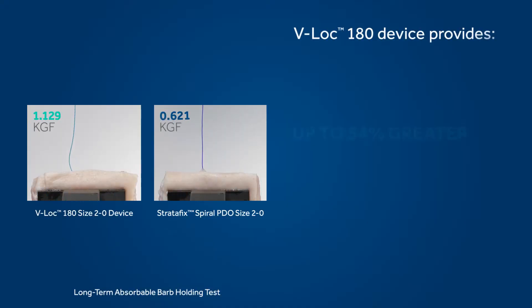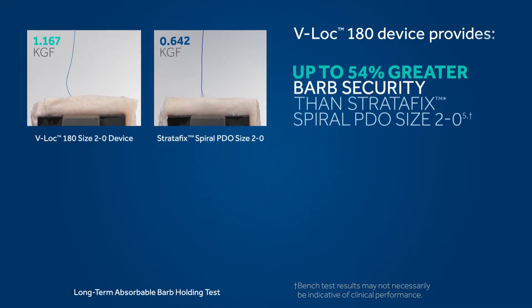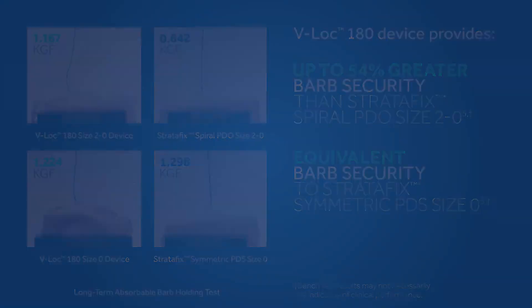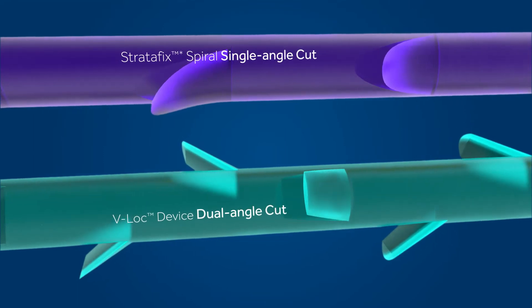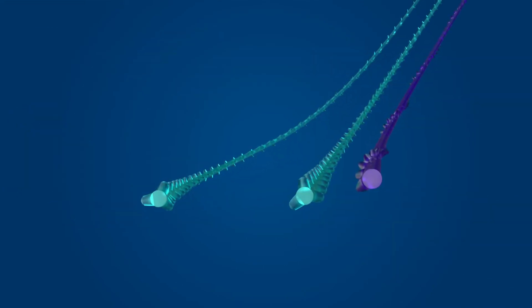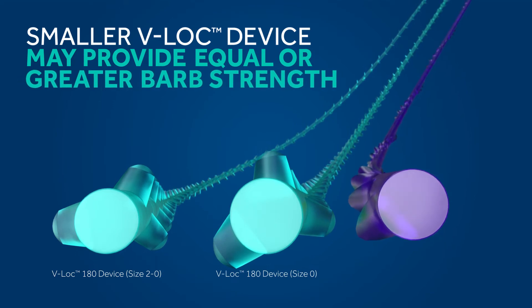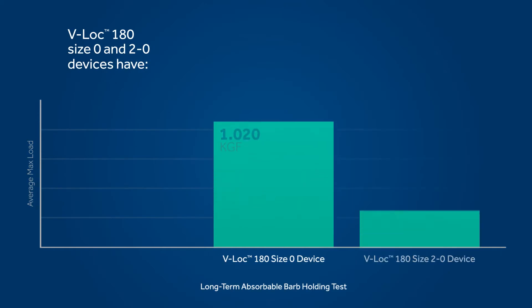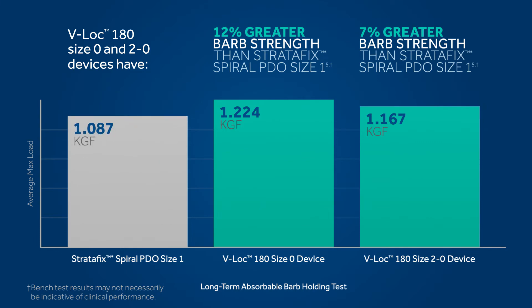In side-by-side barb holding tests, the V-Loc device provided up to 54% greater barb security than Stratafix Spiral PDO size 2-0, and equivalent barb security to Stratafix Symmetric PDS size 0. The dual-angle barbs on the V-Loc absorbable device are significantly stronger than the single-angle barbs on a Stratafix Spiral. In fact, the barbs are so strong that a smaller V-Loc device may even provide equal or greater barb strength than a Stratafix Spiral two sizes larger. For example, the V-Loc 180 size 0 and 2O devices have statistically greater barb strength than Stratafix Spiral size 1.